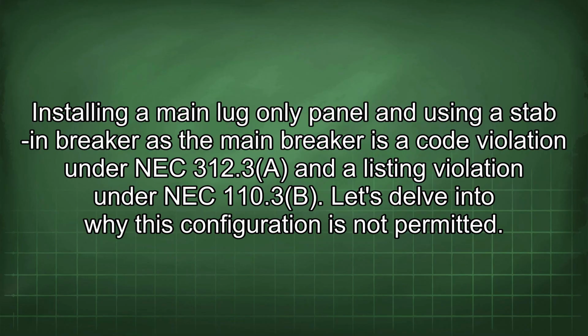Installing a main lug-only panel and using a stab-in breaker as the main breaker is a code violation under NEC 312.3 and a listing violation under NEC 110.3b. Let's delve into why this configuration is not permitted.